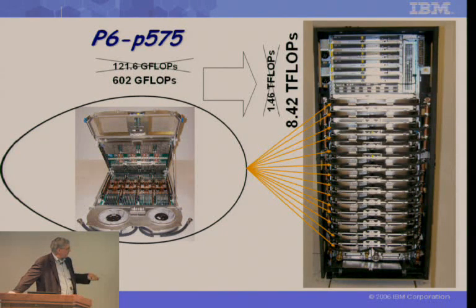We have 14 nodes. You probably can't pick it out, but there's water cooling manifolds up the side here, supply and return. At the very bottom is what we call a water cooling distribution unit that brings in chill water, and that chill water goes through a water-to-water heat exchanger that distributes that conditioned water to all the nodes. This shows a blow-up of one of the nodes.